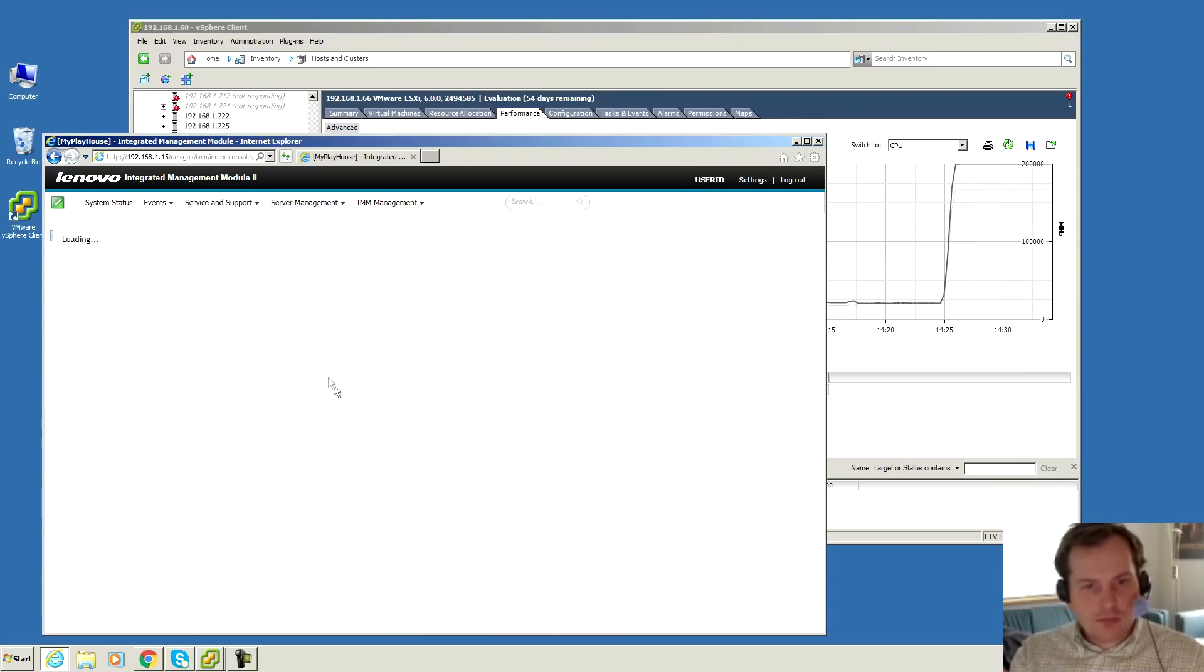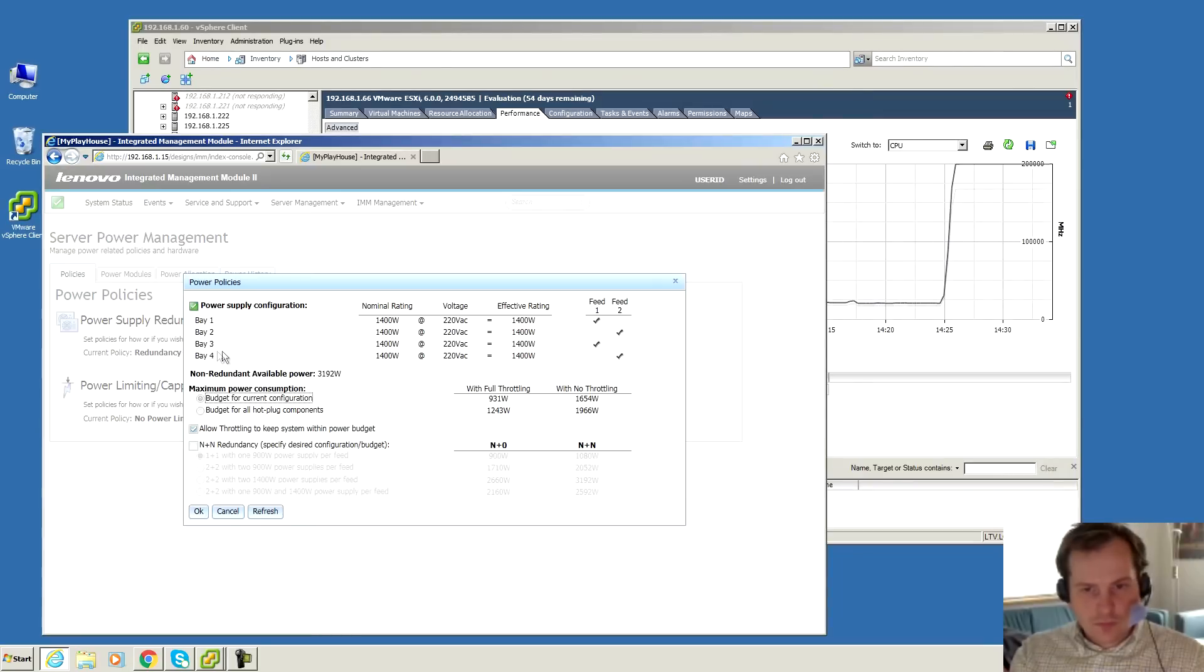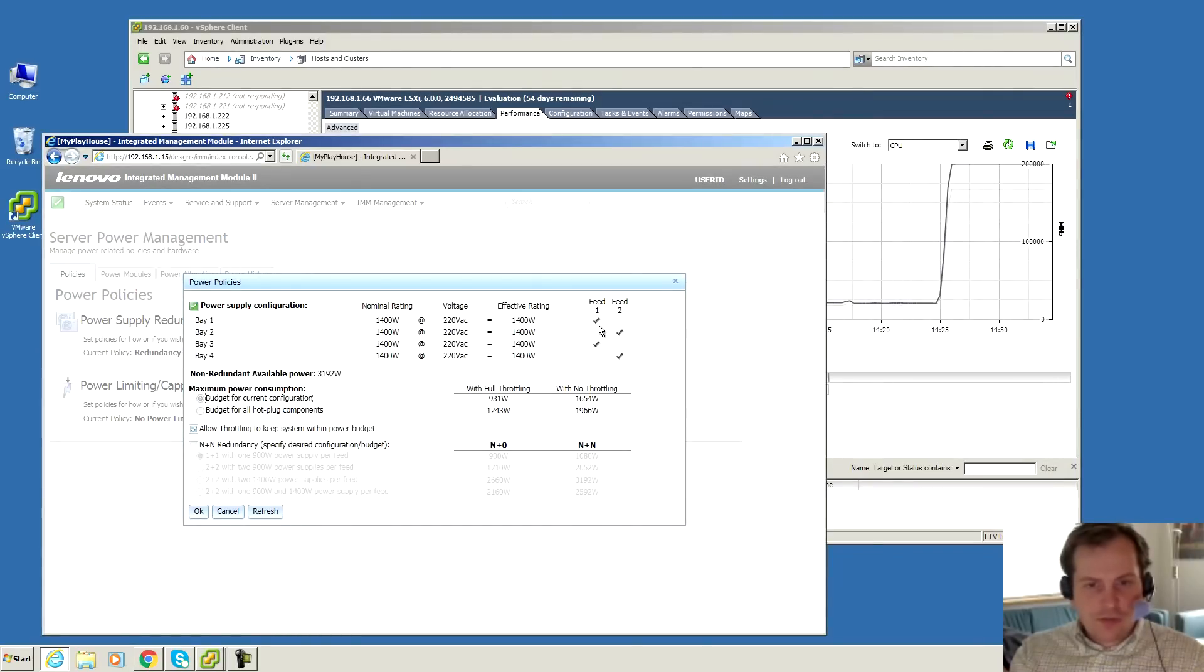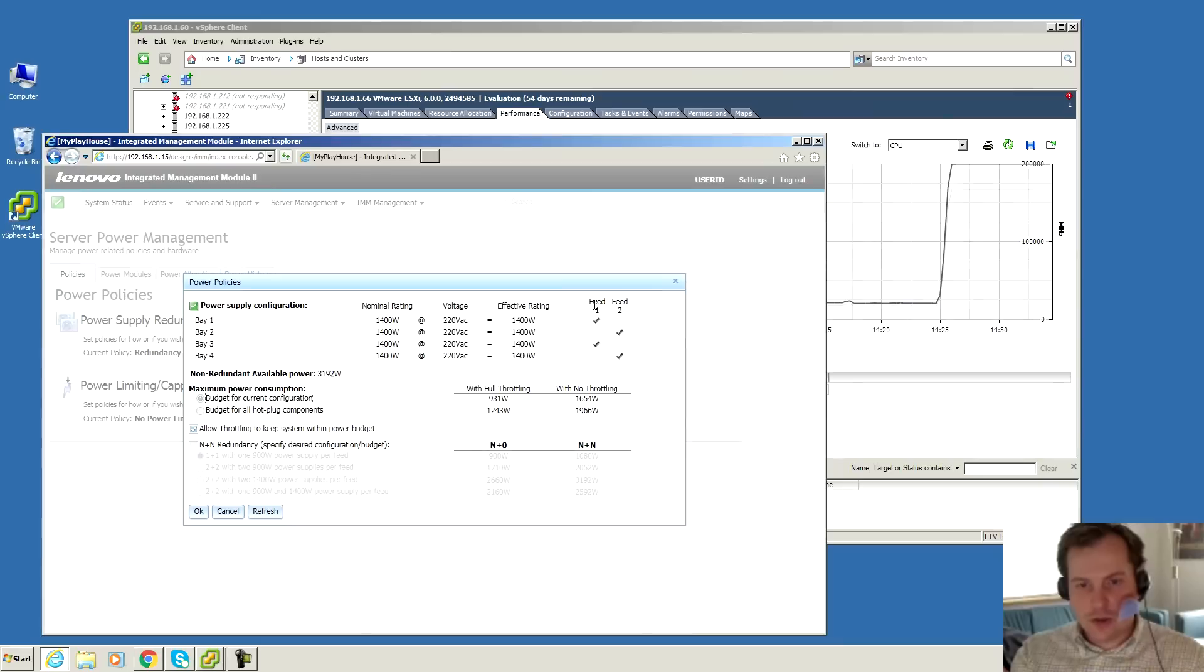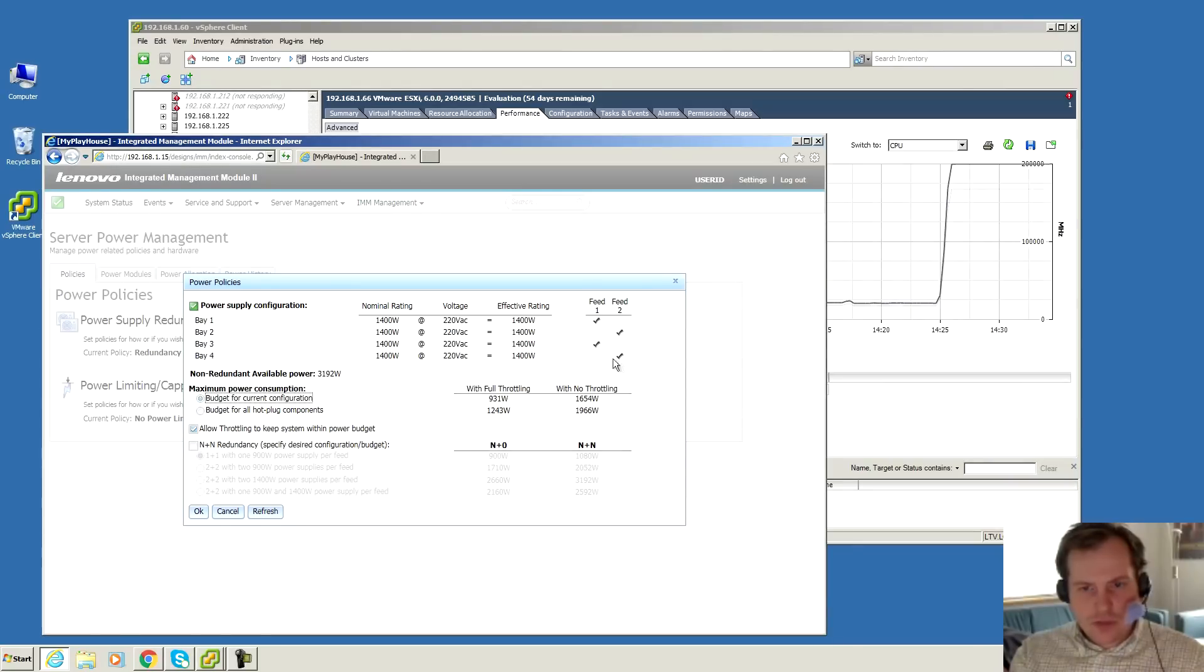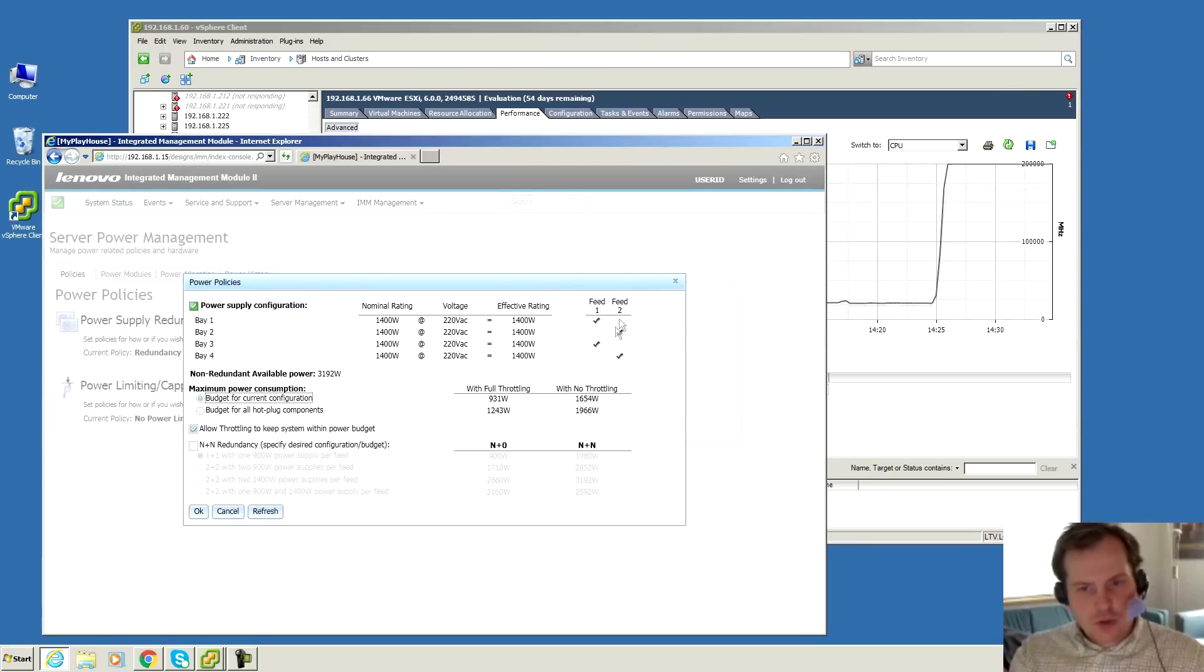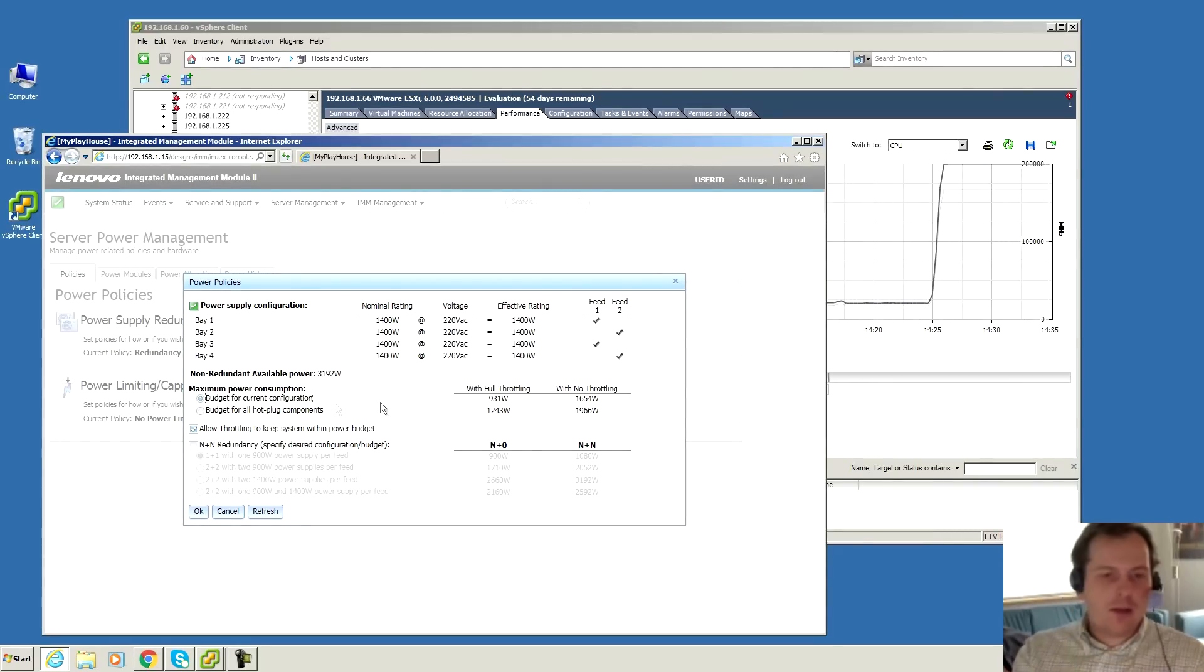Power management there. It might be different if it lost power in feed number two or in feed number one. I have no idea. I don't think I want to test that. I just tested one of each, so it should be able to lose at least two power supplies if they're not in the same feed. If they're in the same feed, I'm not sure what happens. Do we dare to test that?